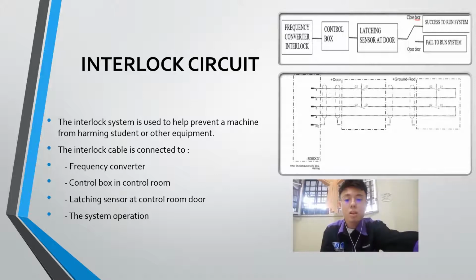The function of the interlock is to prevent a machine from harming students or damaging itself by preventing one element from changing state during the testing. In the circuit diagram above, the interlock is used to monitor the door to the high voltage part of the system, and to monitor if the ground rod is taken out from the high voltage. It can also be a door in a safety fence mounted around the high voltage part. That's all for my presentation.